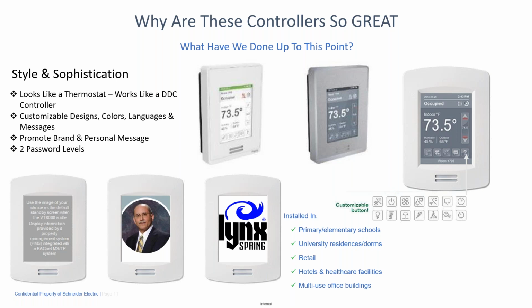Finally, you can also add BACnet short messaging if you're part of a BACnet network or with a Lua program. So like in the controller you see on the right-hand side of the screen where it says room 1705 at the bottom, that's where all the messages show up for like no fan proving switch, frost protection. You can also make that a writable device. So like, for instance, if somebody would check into a hotel room, you could put in welcome Mr. Peacock in that area right there.